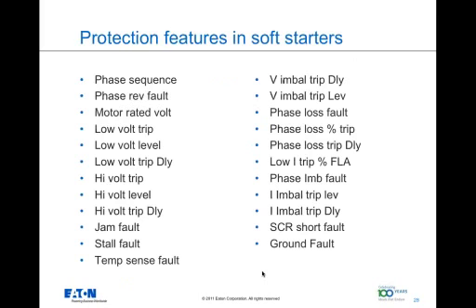The intention of this slide is to introduce you to the protection features that are already embedded into soft starters. Because of this already embedded functionality, you can do away with some of the external devices used for the same purpose and thus reduce the cost. You have protection features like phase control, phase monitoring, low voltage trips, high voltage trips, low current, high current, voltage imbalance, phase loss, SCR short fault, ground fault, temperature sense fault, among others.